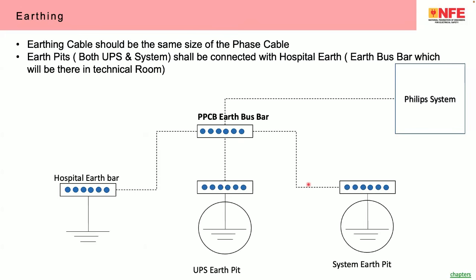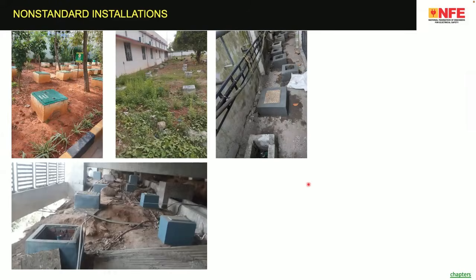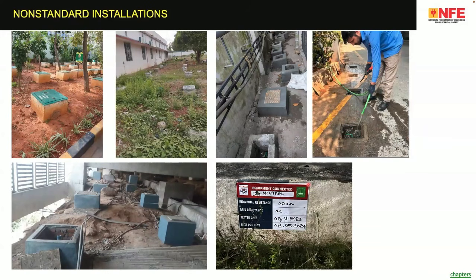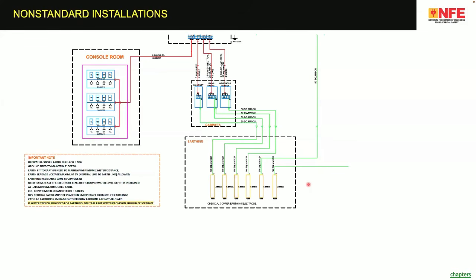And a lot of additional equipment or a lot of additional requirements are being created by the biomedical equipment companies, which is creating a total hazard. I would say if there is an accident from a biomedical equipment, such as a fire or a shock to a patient, the responsibility directly lies on the biomedical equipment supplier because they are violating the electrical safety requirements. Something like this. Non-standard installation. Every biomedical equipment demands so many earth pits, with zero point one or less than 1 ohm resistance. This is a blatant violation. These are non-standard installations.